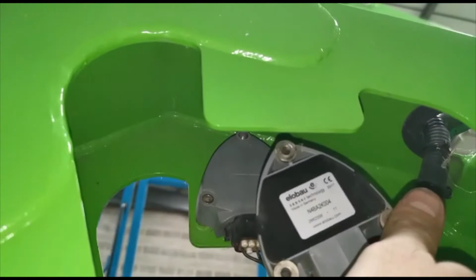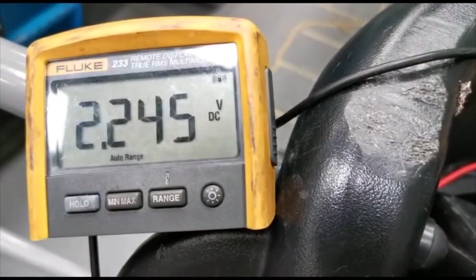And yeah, let's fit them on, and I will try to recalibrate the machine again and test it one more time. Okay, so I have the sensors refitted as they should be. What I want to show you, I still have this angled. So the cage is still angled, but the machine is up and running now. The voltage reading on both sensors should be close. So one is 2.24, okay, and the other one 2.25. A slight difference in reading is not a big deal, because that's being compensated by calibration. But they're reading as they should, both in the same direction.